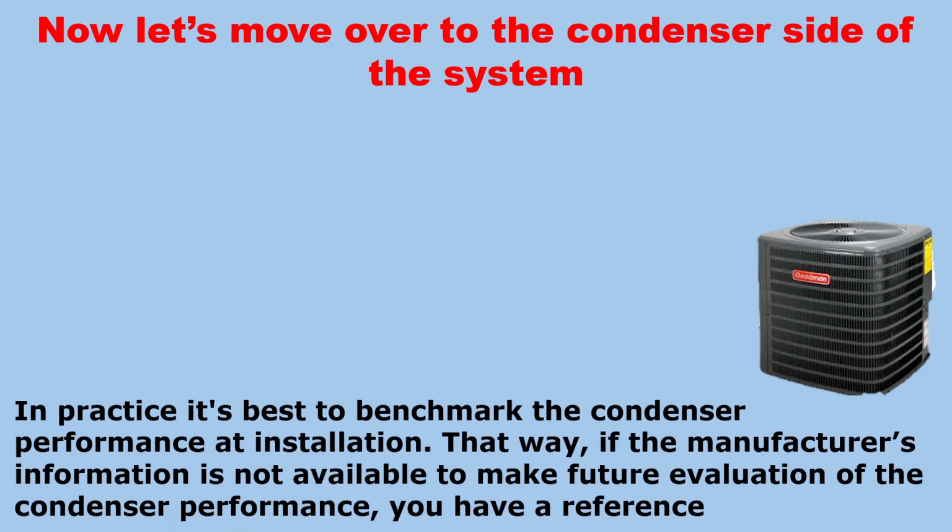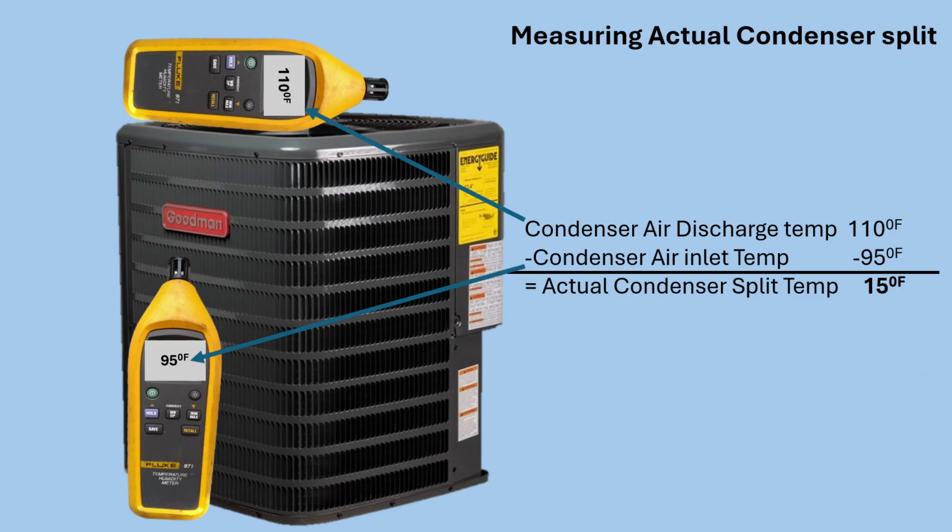In practice, it's best to benchmark the condenser performance at installation. That way, if the manufacturer's information is not available to make future evaluations of the condenser performance, you have a reference. But I have seen this many times, that you think the condenser design temperature differential is 20 degrees and it's not even close. So, you want to keep that in mind.